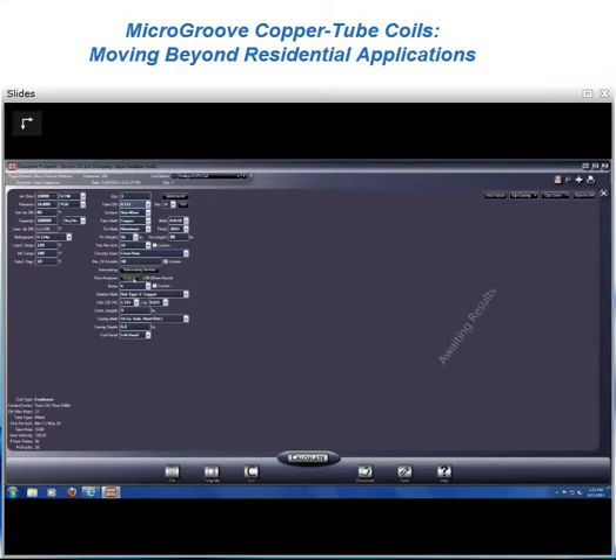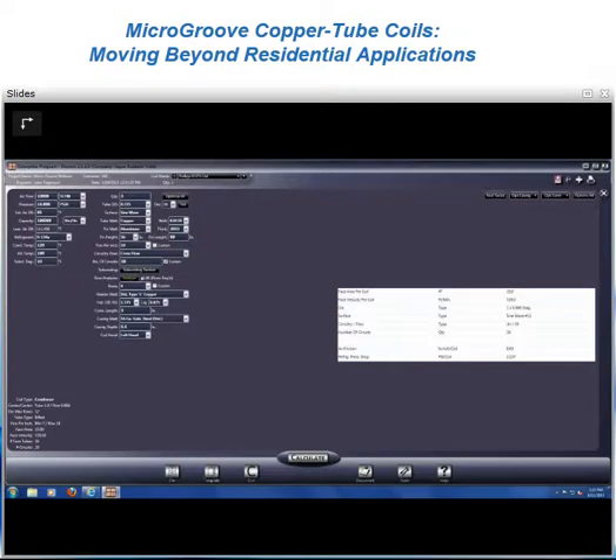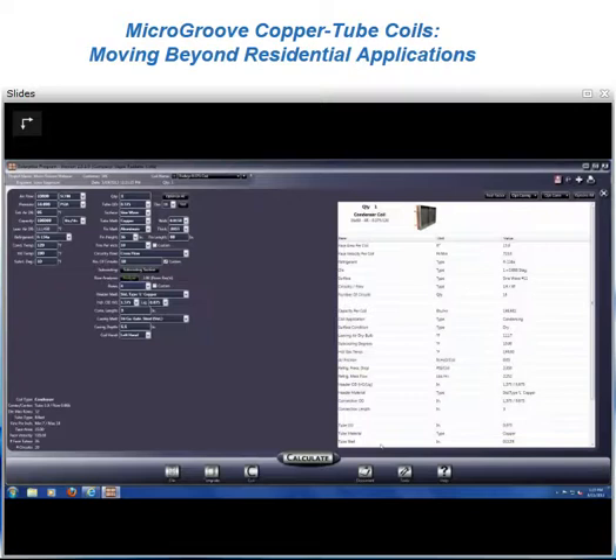Cross-flow arrangement, we've input the number of circuits for the coil, and we'll come down to how many rows we need to meet the performance we've requested. And it tells us 3.9. We have some preliminary data here, but we can't build a 3.9 row coil. Really close to 4, so we'll rate a 4-row coil. If you wanted more, you have options here as well. So let's do calculate on this coil to get a full printout of the performance.